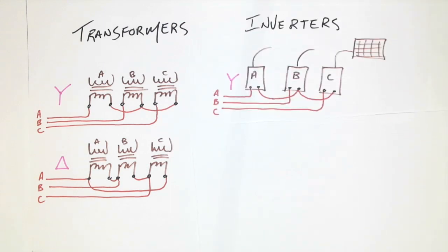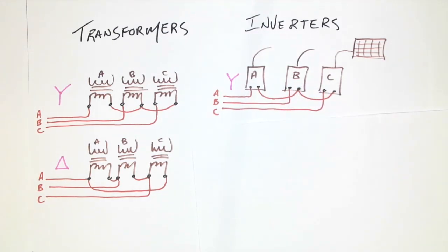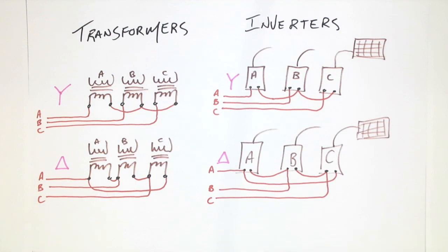Now, this isn't done nearly as much as it was in the past, and that's because now we have solar PV inverters that can give us a nominal three-phase system voltage rather than trying to assemble our own three-phase connection by using single-phase inverters. Depending on the brand, we were able to assign each of the single-phase inverters to a particular line or phase, and then you had the choice. You could connect them in either Y formation or delta, depending on the voltage requirements and the application.